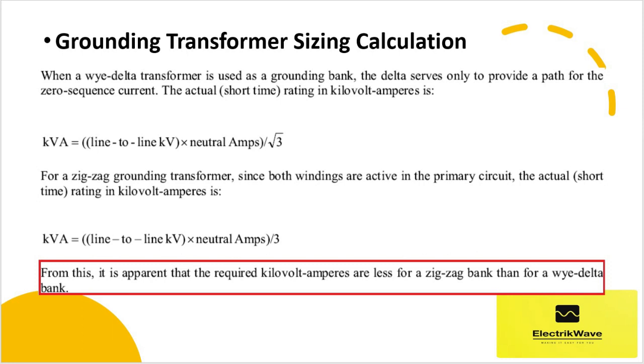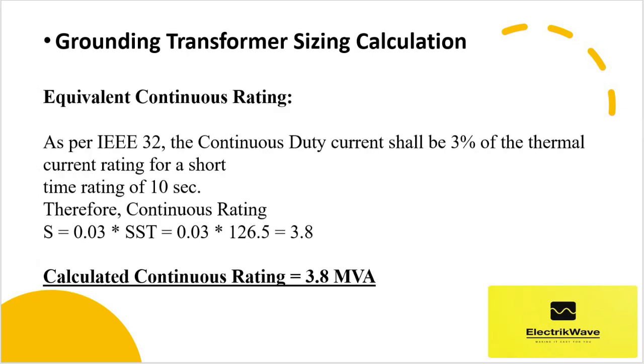From this comparison, it is apparent that the required kilo-volt-amperes are less for a zigzag bank than for a Y-delta bank. Next, let's calculate the equivalent continuous rating as per IEEE 32.